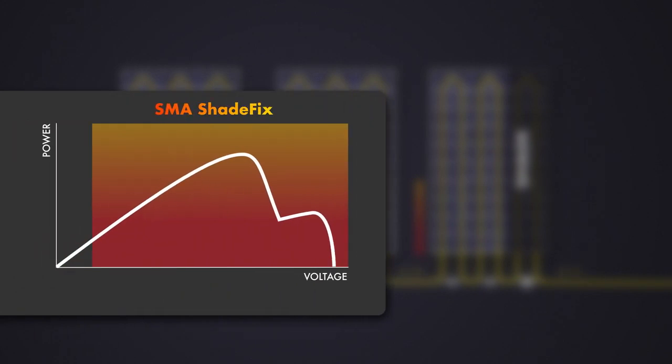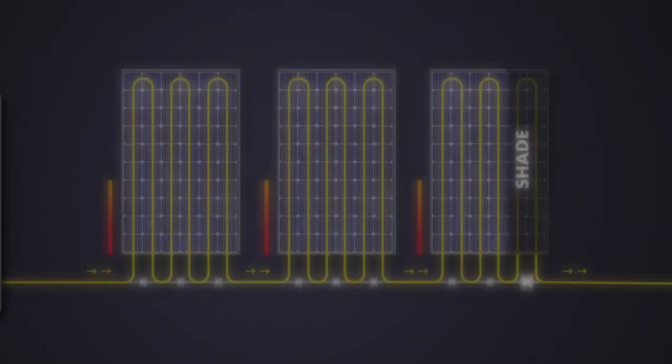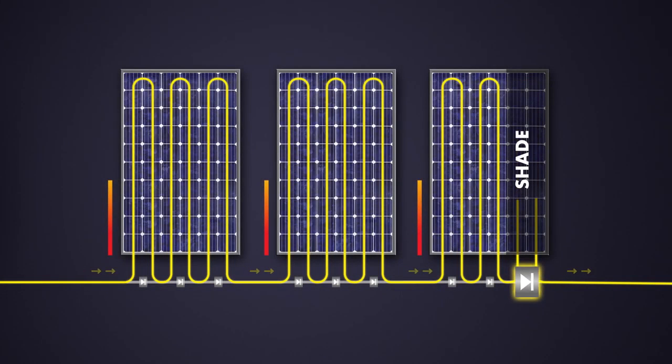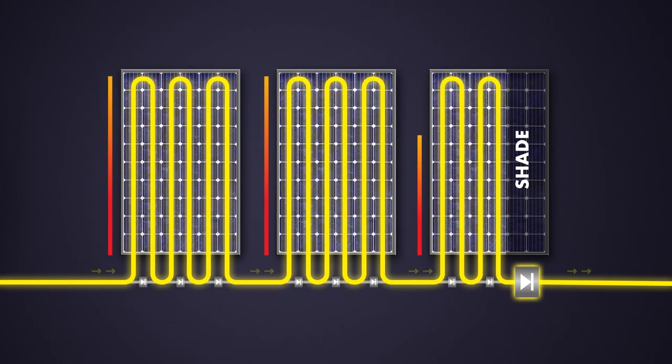Let's see what happens to the partially shaded PV array using SMA Shadefix. The inverter will recognize the higher global maximum powerpoint at a lower voltage, and will set its operating point accordingly. Due to the technical properties of PV modules, this will force the bypass diodes of the shaded PV module into conduction.